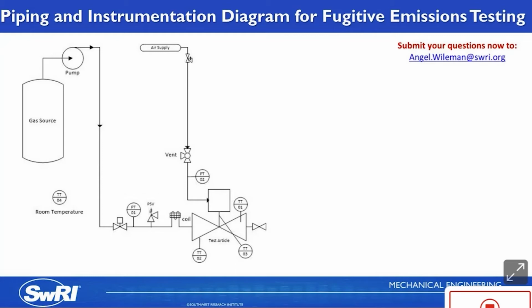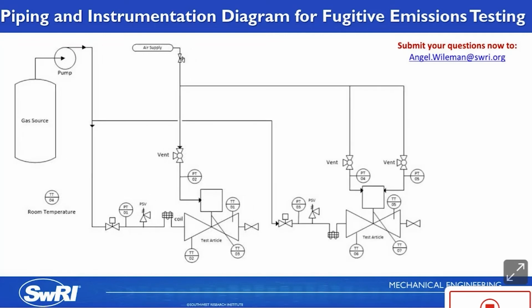Now, if you were to qualify another valve at the same time, you could have a setup like the one shown here, assuming that you have similar thermal requirements, and that way you can heat and cool them simultaneously, which will speed up time. But you need to be able to isolate each valve from the pressure source and pressurize them independently, which is why we have our automated isolation valves upstream of each valve. If not, then it's going to be hard to determine where the leakage is coming from if you have elevated backgrounds and which valve is actually leaking. Also, I added another PSV for the second valve, assuming it has a different pressure rating. If it didn't, you could plumb both of them together. And this second valve is plumbed assuming that it's a double acting actuator. So you would need to apply air pressure on both sides, and you would need to measure pressure on both sides for your opening and closing torque measurements.